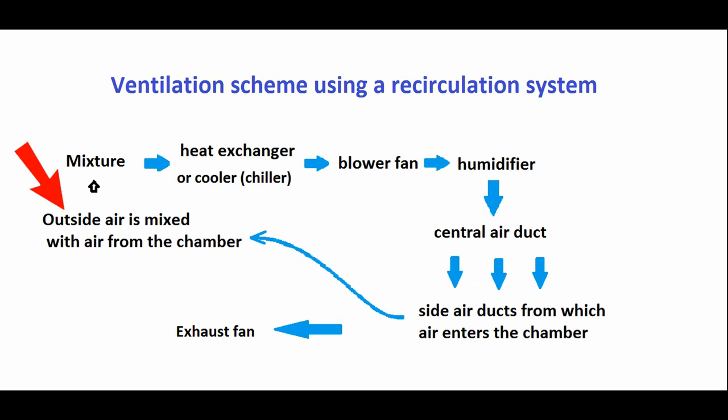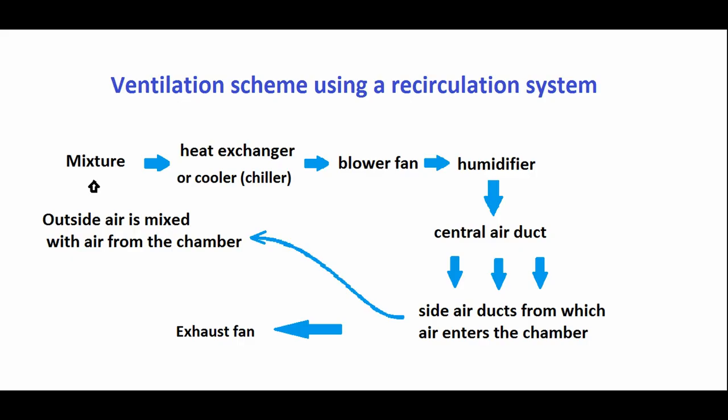First we need to mix the outside air with the air from the grow room. Pipes and dampers are used to mix the air. The dampers regulate the amount of air that comes in from outside. The ventilation system that uses the internal air of the chamber is called recirculation, and the air itself is called internal or recirculated air.